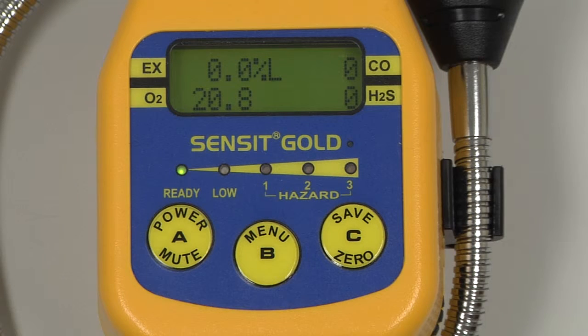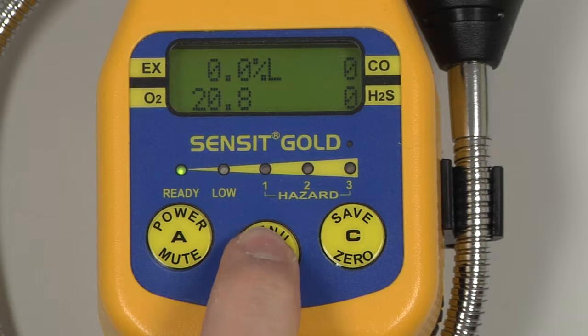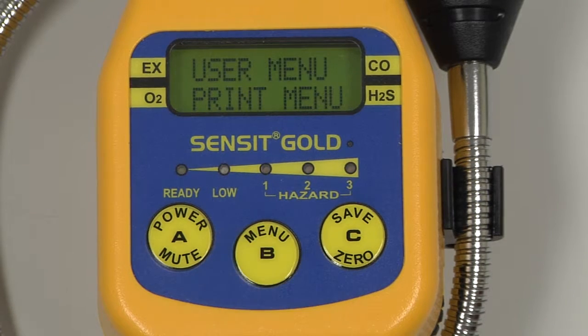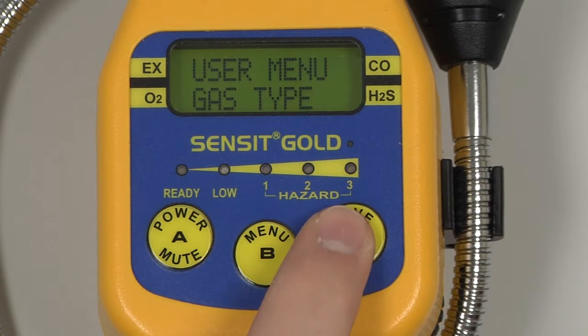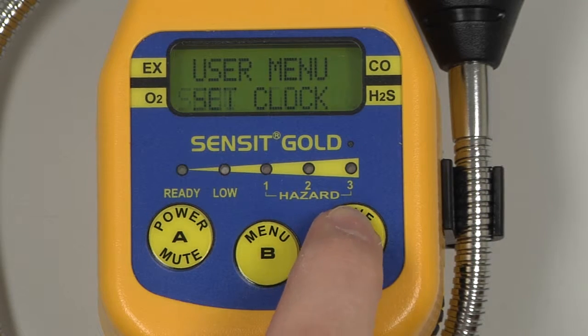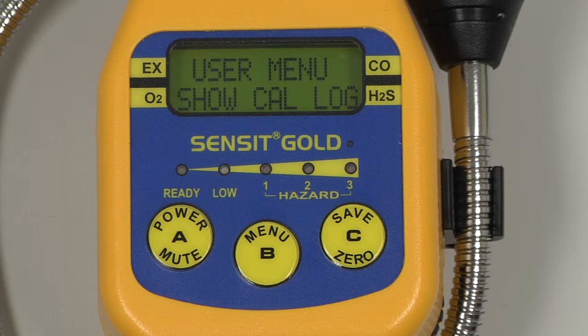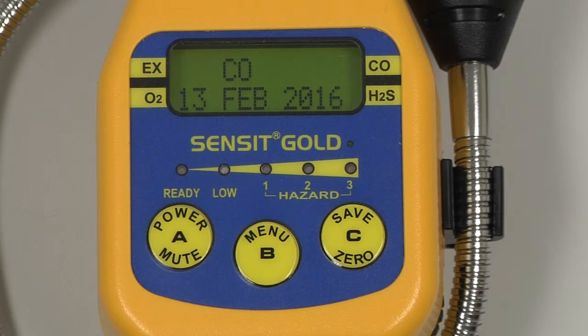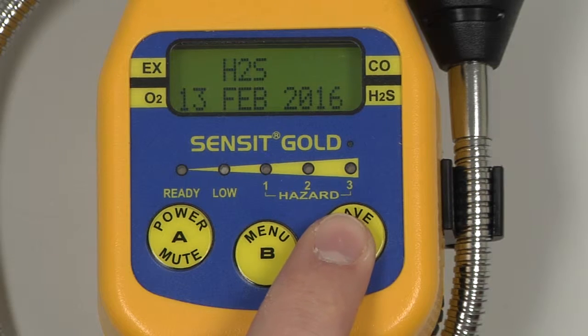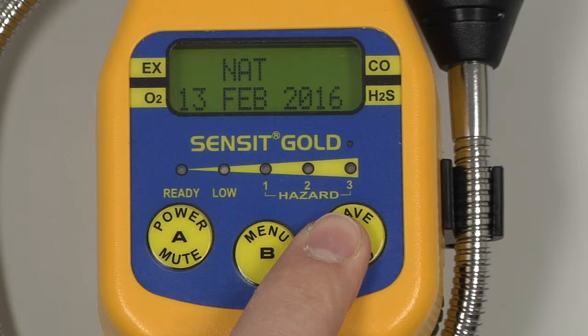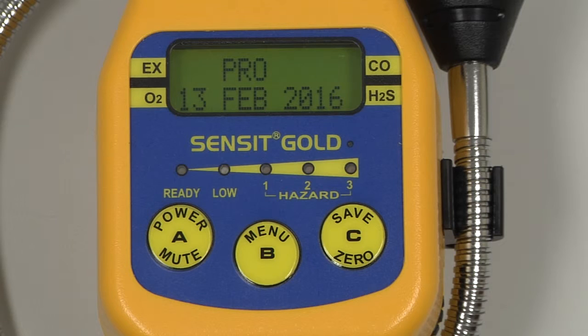To verify the calibration date, enter into the user menu by pressing and holding the B button, and scroll through the menu by pressing and releasing the C button until Show Cal Log appears. Select by pressing and releasing the B button, and on the display we will have the most recent calibration date for each sensor. So in this case we have CO, and we can scroll through by pressing and releasing the C button to C, H2S, LEL, natural for 100% by volume methane, and propane.